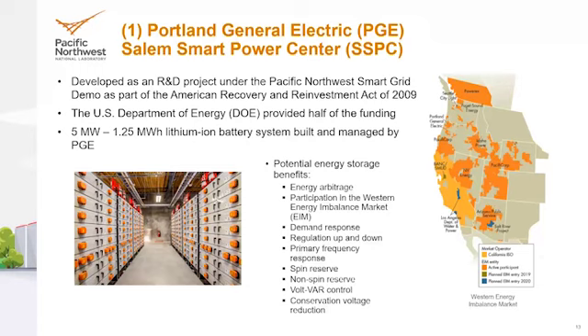At 5 megawatts, 1.25 megawatt hours, it's quite a shallow energy storage system from an energy-to-power ratio perspective, meaning that if you provided 5 megawatts continuously, you would fully deplete the battery's energy capacity within 15 minutes. That has significant implications for the economics of the system.